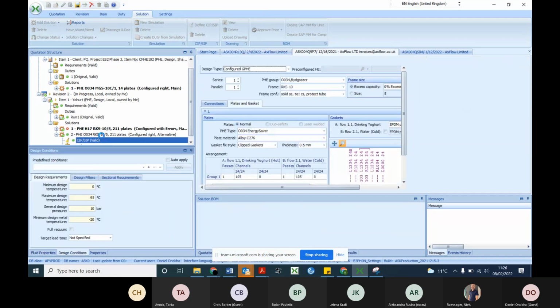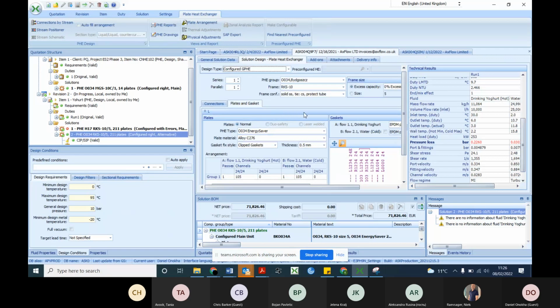Another thing, if you go back to your heat exchanger, if we then look at the result over here, you see your flow regime on this is called MI, meaning that you are below laminar flow regime. You simply will have a maldistribution in this heat exchanger. Imagine you have all these channels to distribute the fluid in. It will only run in some of them because you have that many parallel channels.